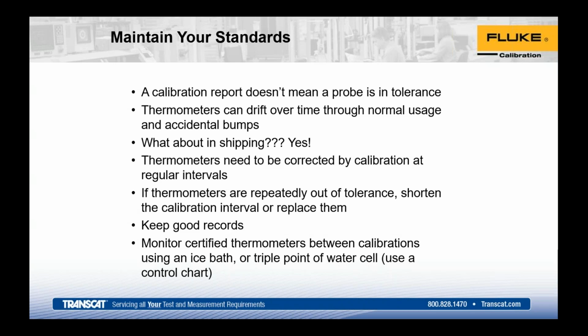You're going to want to calibrate at regular intervals, but one thing people don't tend to do is monitor in between calibration cycles. Unfortunately, once you send something out and a Cal Lab receives it and they recalibrate it, they can only report on what it's doing right now. If there was a bump or something that is going to cause you an out of tolerance that say happened 6 months ago, there's no way for a lab to tell that. They can only report on what it's doing right now.